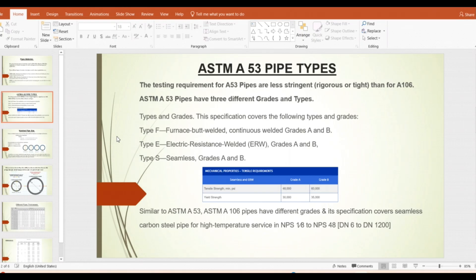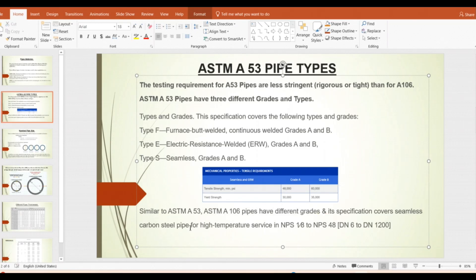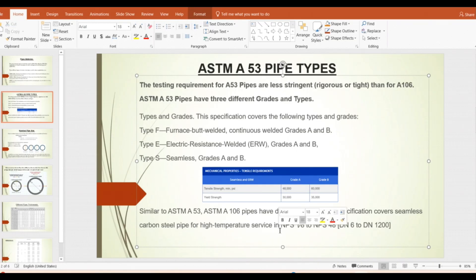Based on client requirements, the client will specify whether they need only seamless or only welded pipe. For the grade, clients almost always recommend Grade B because of the higher tensile and yield strength. Similarly, ASTM A106 exists with different grades and applications. As mentioned, ASTM A106 is mainly for high temperature; however, since chilled water temperature is very low — around 4.4 to 5.5 degrees, maximum 16 to 20 degrees — ASTM A106 can also be used for chilled water.